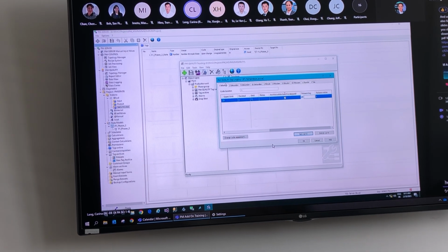And at the moment this tag value changes to 1, then we start recording the values of this curve in the cycle we have configured here, so in 1 second. And if this tag is going to 0 again, or to another value which is not that one here, then we stop the recording again.